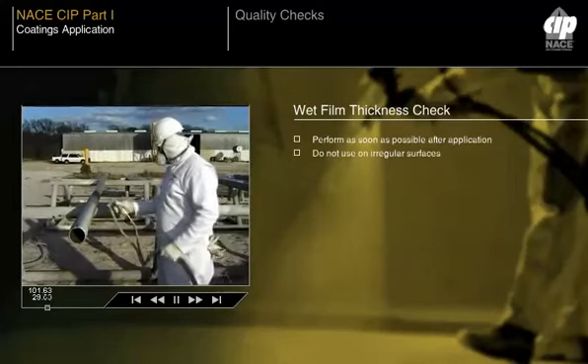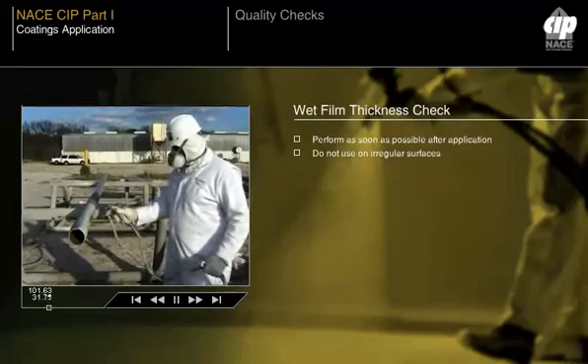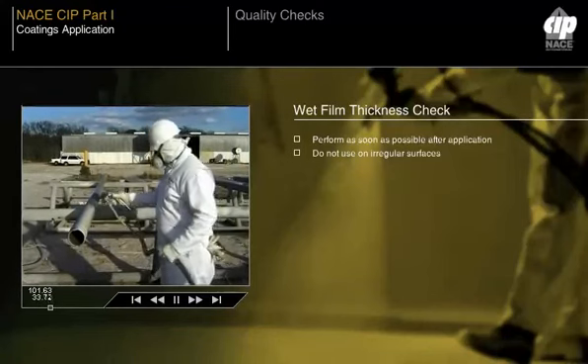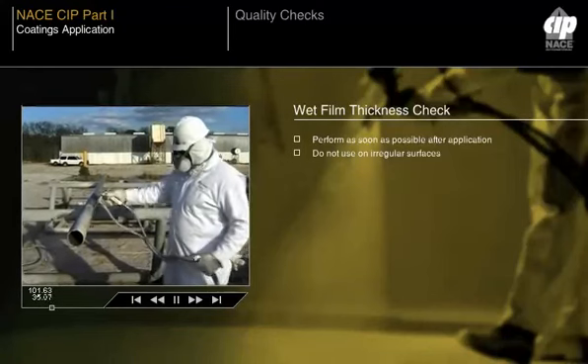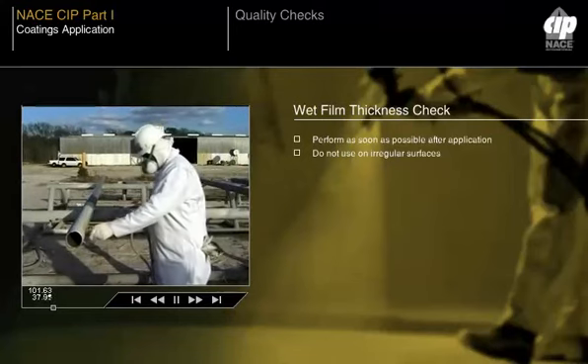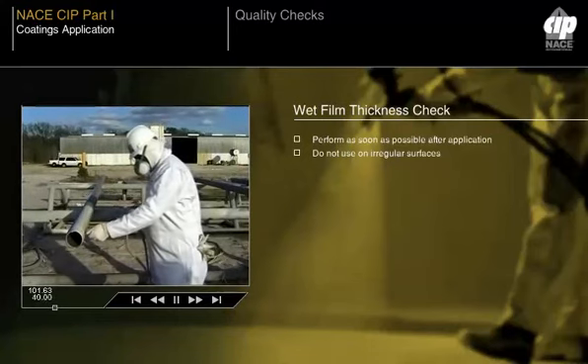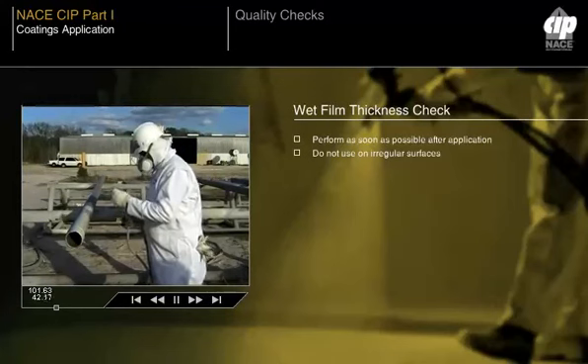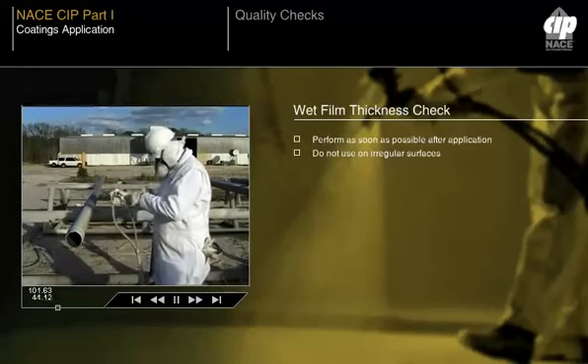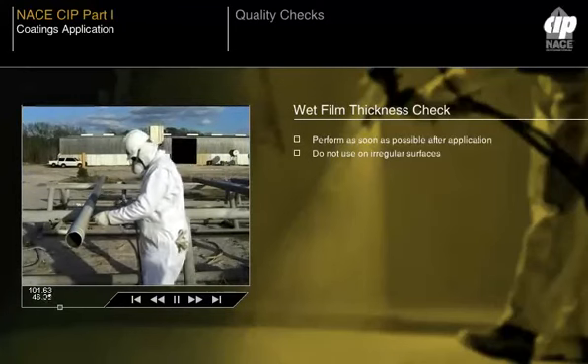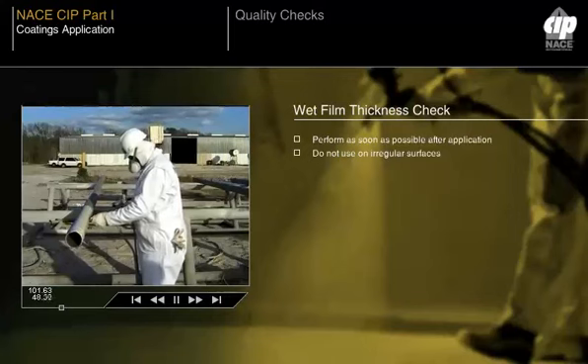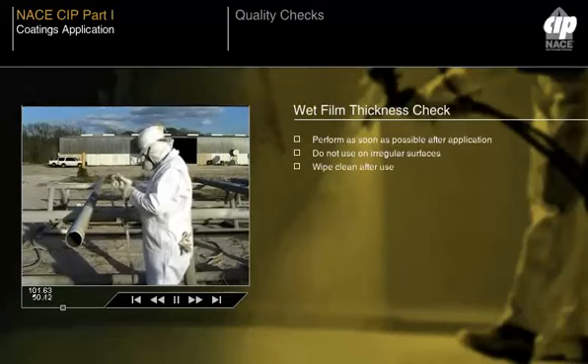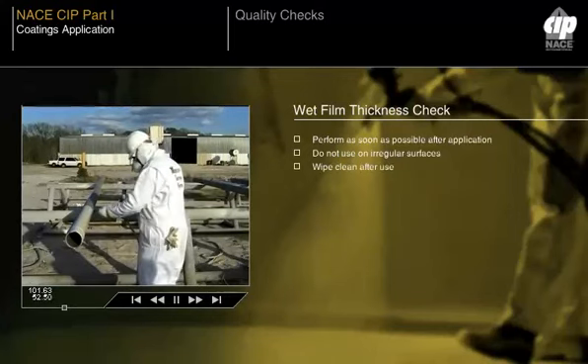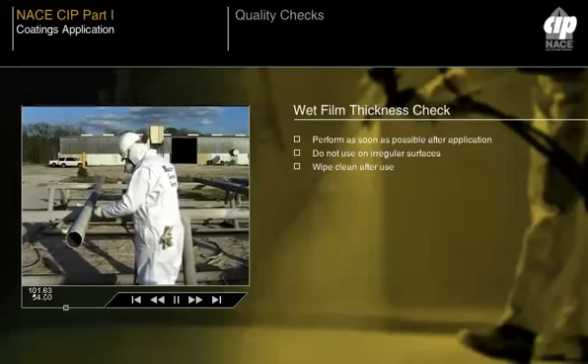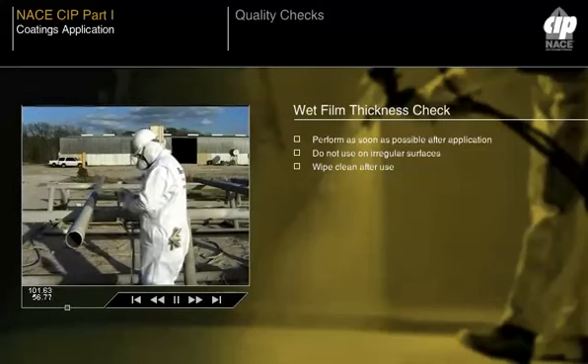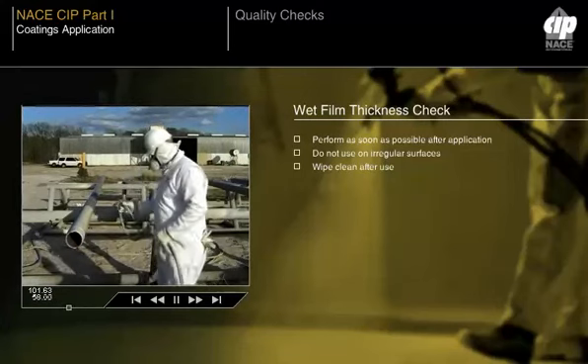Care must be taken that the instrument is not used on any surface irregularities that might distort the measurements. On curved surfaces, readings should be made along the length of the curve rather than across its width to prevent irregular wetting of the steps. The gauge must be wiped clean of all coating after each use to prevent the possibility of inaccurate readings due to coating buildup on the gauge.